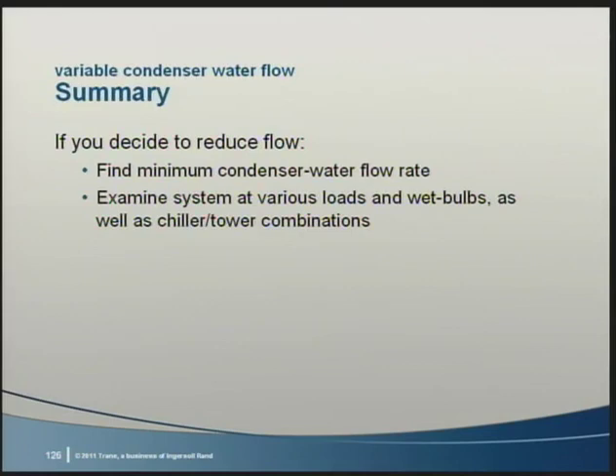If you do decide to reduce condenser water flow rates during operation, know the minimum condenser water flow rate for your system. Then, to find efficient operating points at various loads and ambient conditions, take the time to examine the system at all those loads and ambient wet bulb temperatures. What occurs in real life is quite different than what the AHRI chiller rating standard assumes. And remember that over the year, the number of chillers and cooling towers operating may also vary.